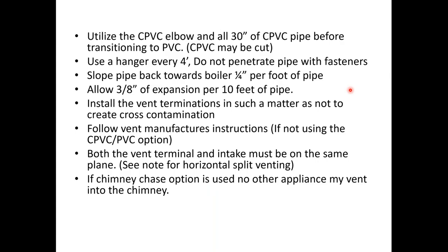A few things with our products. We're going to recommend that you use 30 inches of CPVC prior to transitioning to PVC. PVC technically has no vent listing. If you were to call Charlotte Pipe and ask them for the ASTM numbers for PVC being listed as a gas vented appliance, it doesn't exist. PVC is technically not approved for venting gas appliances. It's been left up to manufacturers to do so. I would love to see everyone vent in polypropylene, but the industry's still kind of stuck on PVC.